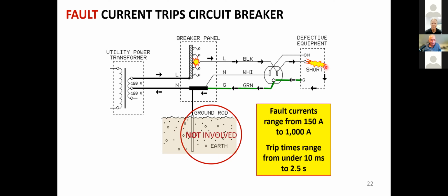But if there's a fault in the equipment, now we have current flowing from the hot side of the power line to the chassis and the ground connection. And this carries it back as an alternate path. And the current in this loop is now high enough to kick the breaker out. And at 150 amps, believe it or not, it can take several seconds for that breaker to react. Only at 1,000 amperes will it kick out in less than a cycle of the AC.